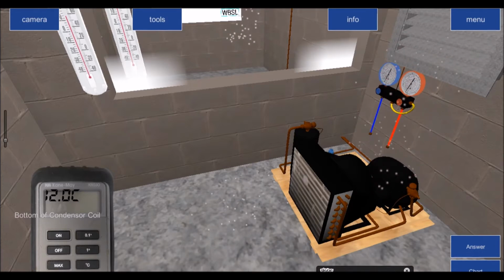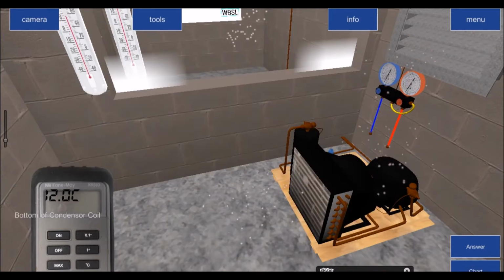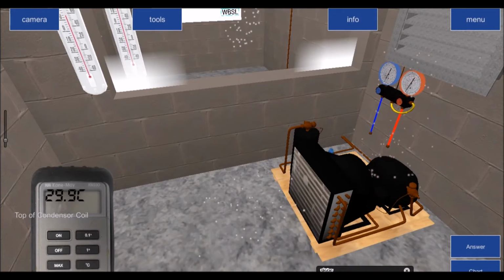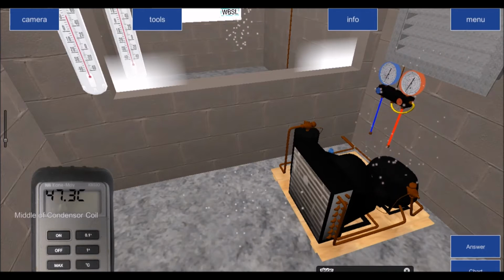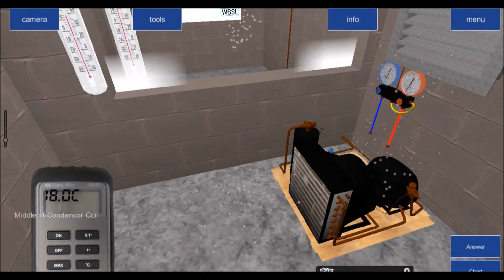But getting back to the original question, which was, is the head pressure too low? Is my condensing temperature or pressure too low? Okay, so effectively how I answer that question is I say, okay, I use my thermometer in the middle of my coil, in my condensing zone, and I'm getting a reading of 18 degrees Celsius, and my air-on temperature is 20 degrees Celsius. So for an air-on temperature of 20 degrees Celsius, what should my condensing temperature be?